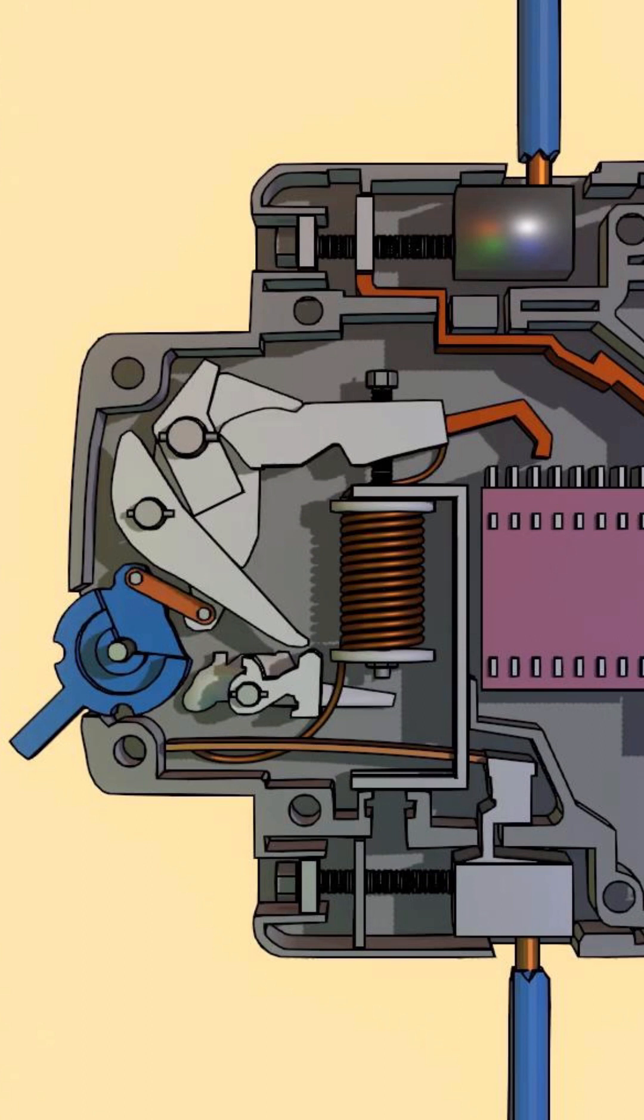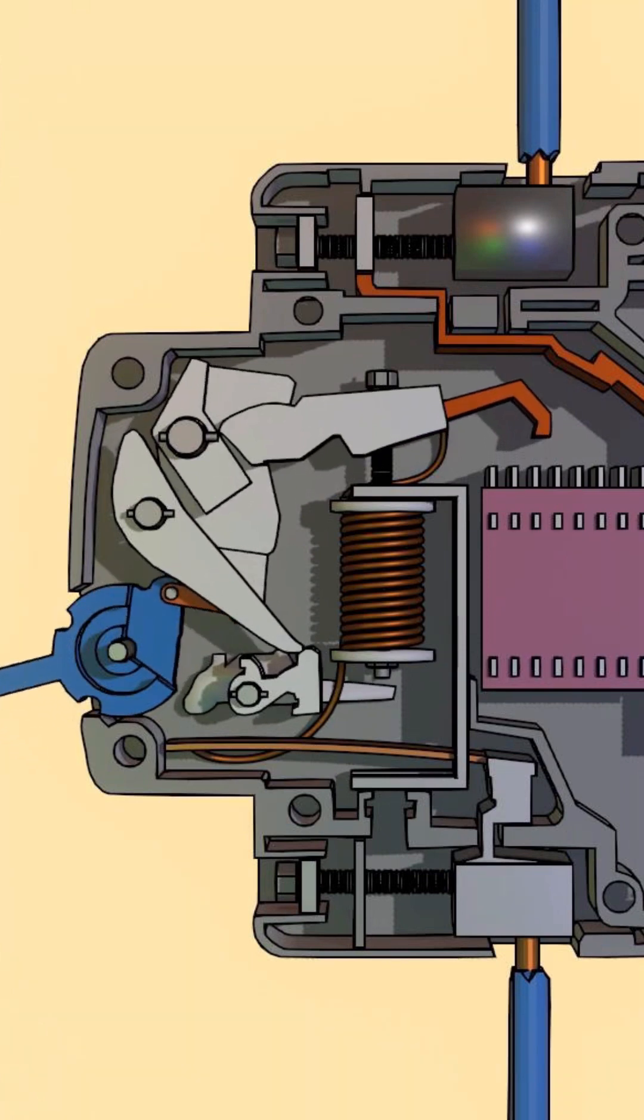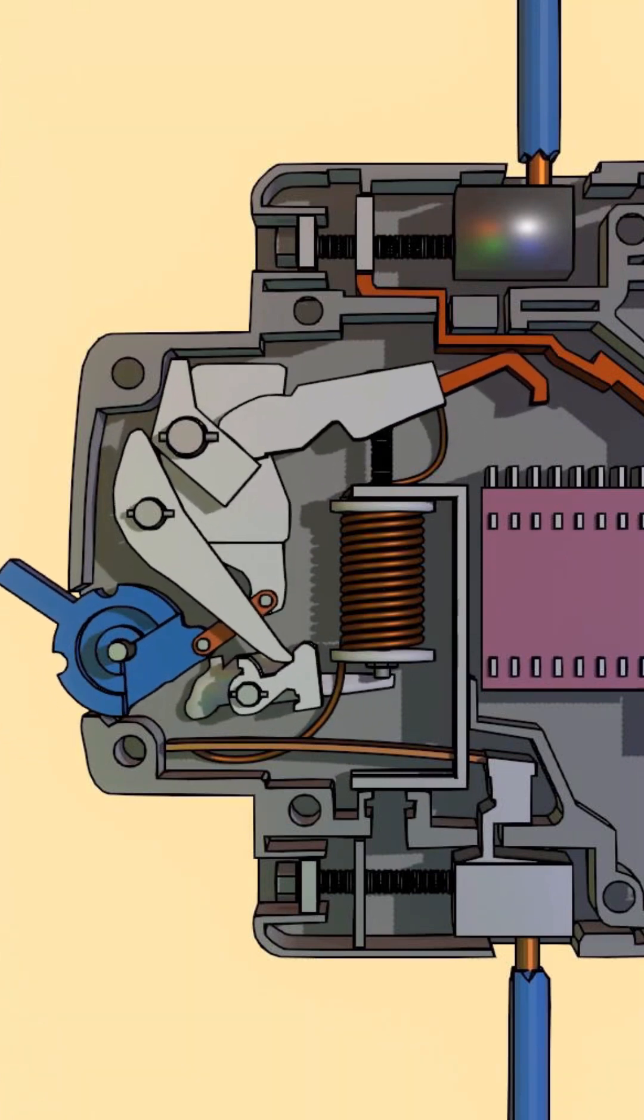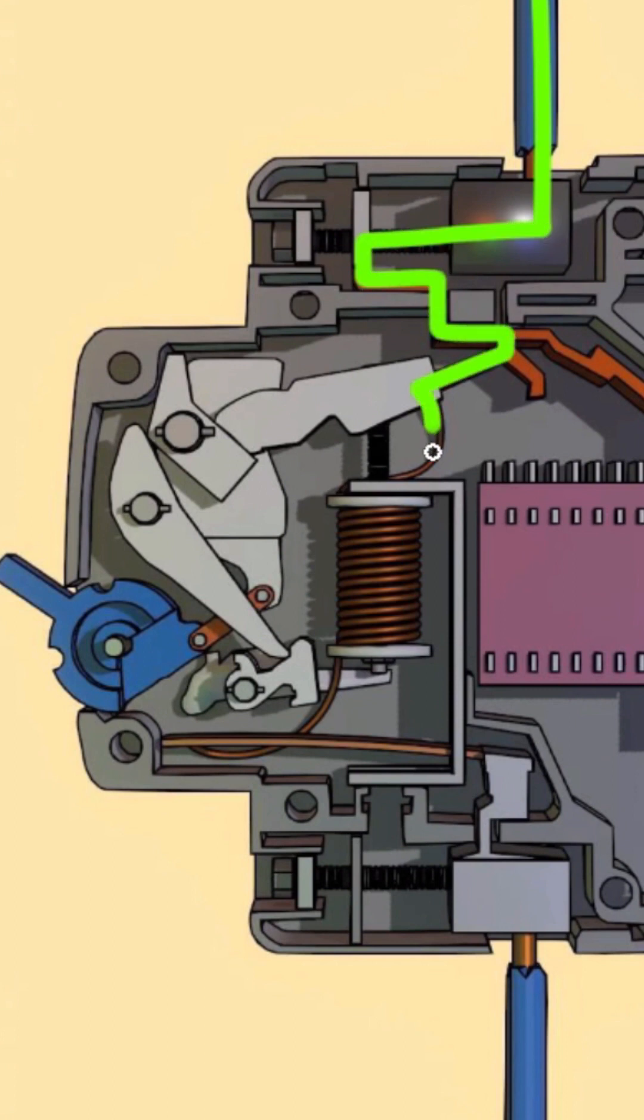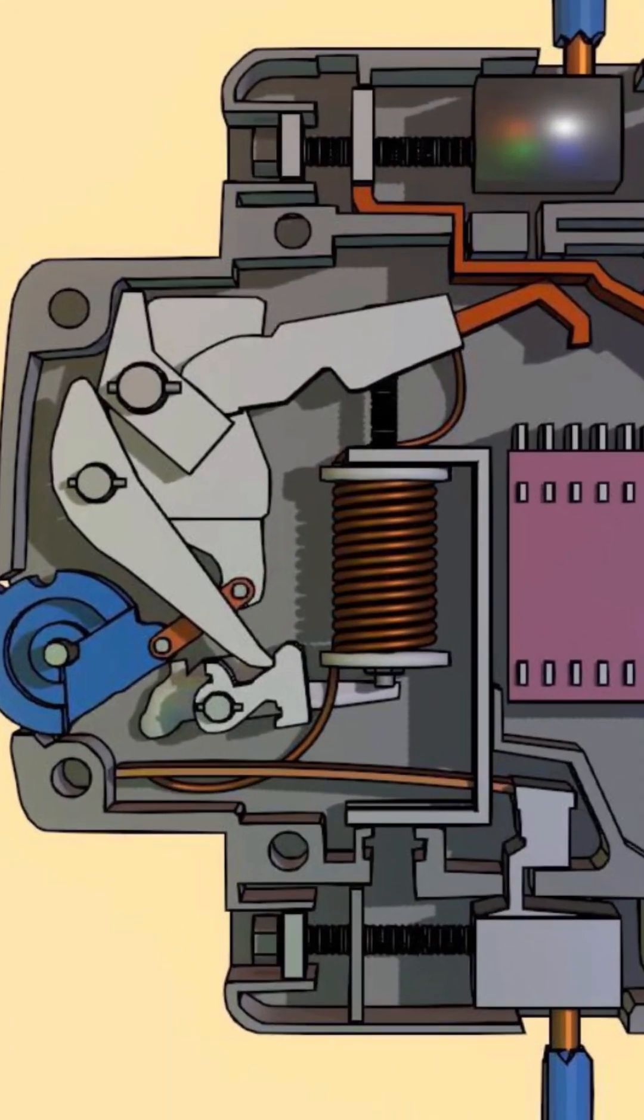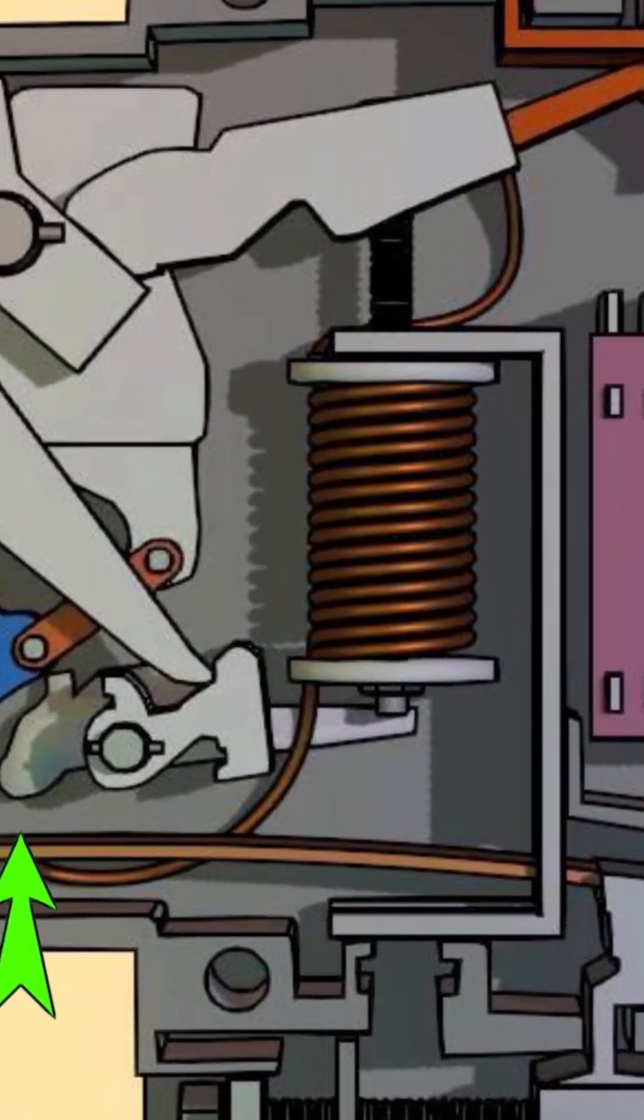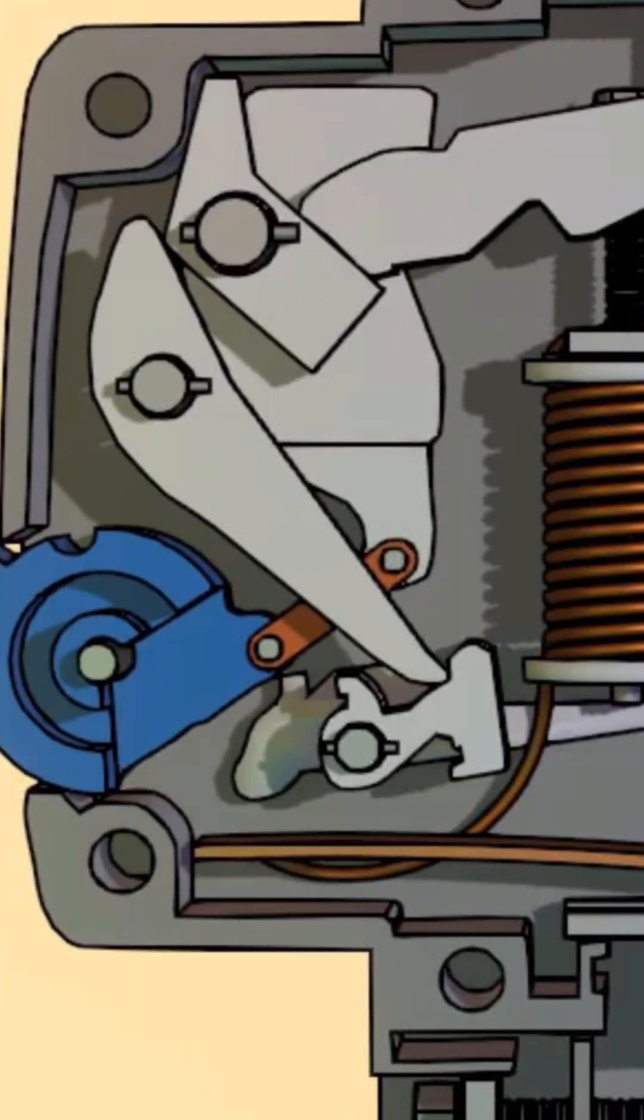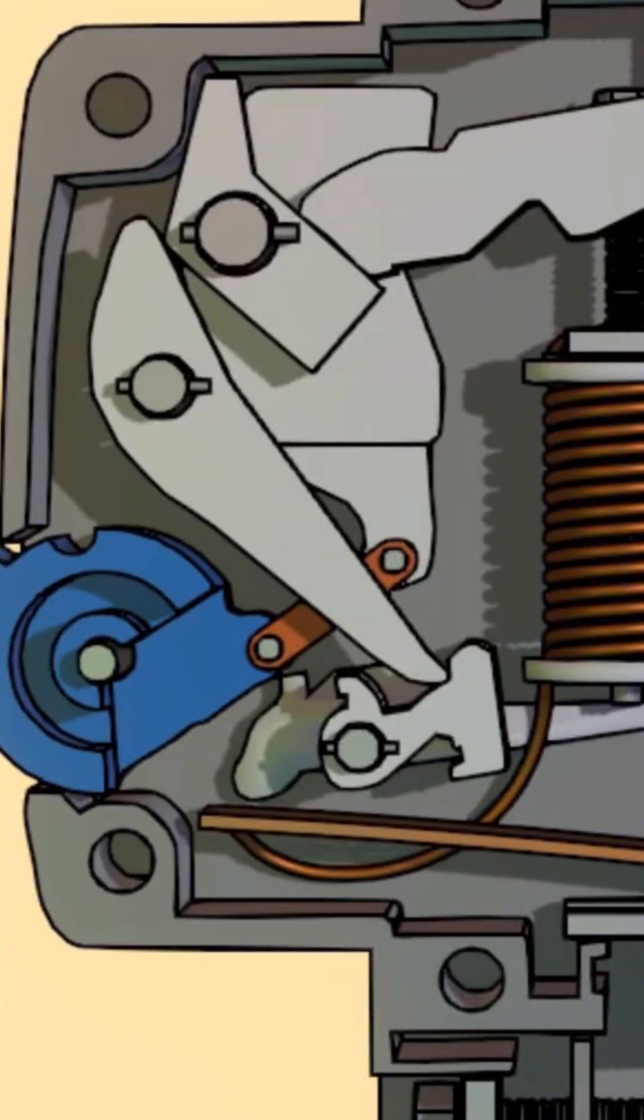Now if there is an overloading condition, the current beyond the limit flows through this path and the bimetallic strip, due to high current, heats up and bends. It pushes this point and as soon as it does, this spring-loaded lever is released. The mechanism rotates and the moving contact moves away from the fixed contact, breaking the circuit under overloading.